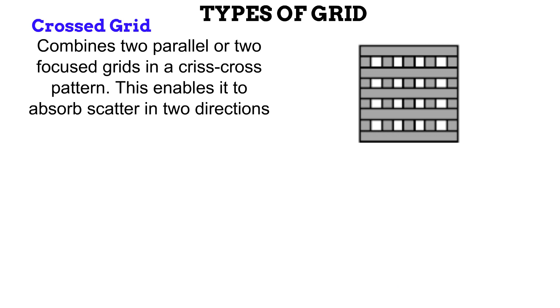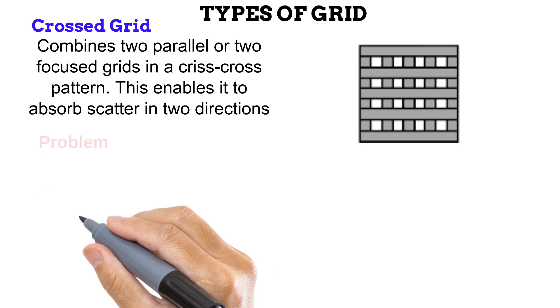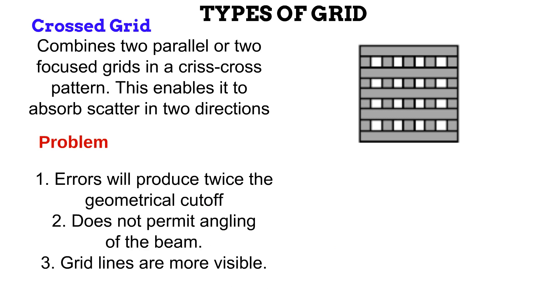The next type is the crossed grid. In this type, two parallel or two focused grids are combined so that their lead strips intersect each other at 90 degrees, giving it the resemblance of a chessboard when viewed from above. It is designed to absorb scatter in two directions. The problem is that because it has twice the lead strips, any error in its use will produce twice the geometrical cutoff. Also, because the lead strips are in two directions, you cannot angulate the beam — only straight X-ray beams can be used. The presence of more lead strips also makes them more visible, producing reduced detail.